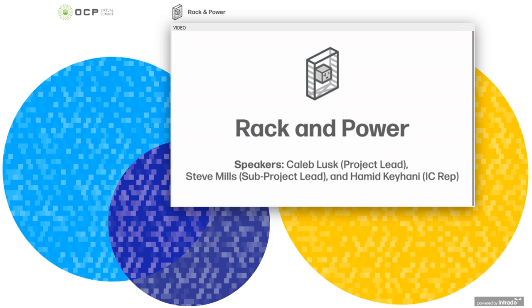I'll take the next question from Mark Lerner. Is there a 1OU PowerShelf design that provides two AC inputs that each fully power all 6 PSUs? What I see now is that input 1 powers 3 PSUs and input 2 powers 3 PSUs, which is not full AC redundancy. Let me explain slightly more. There are two ways to think about redundancy. You could have N+1 redundancy, or you could have N+N or 2N redundancy. What we have designed for the 1U shelf is N+1.